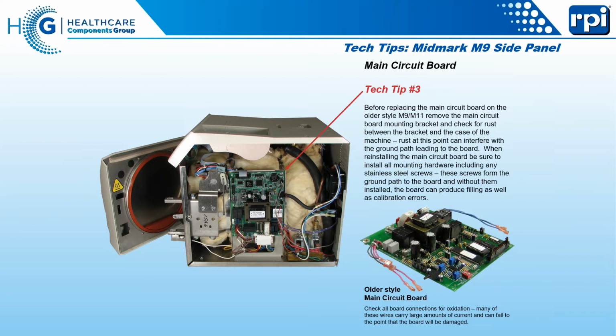On this older style machine, mounted behind this board is a metal bracket, kind of like the other one, but the bracket stays in the machine. Now, when Midmark designed this -001 through 19 version, they did not put in a ground path between this board and the machine. What they did was put a screw, I think in that corner, a black oxide screw. It goes through the board, picks up the ground, goes into the metal bracket mounted behind the board, down to the bottom of the case where there are 2 additional bolts, and then to case ground.